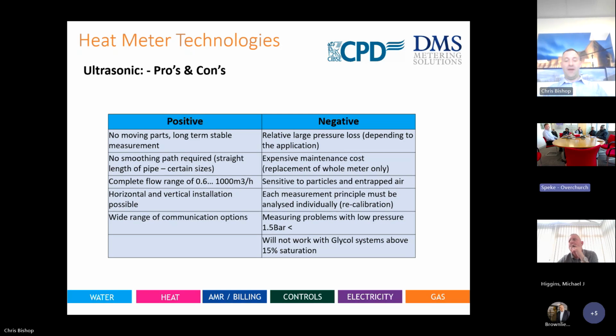Maintenance cost. For example, you have a lot of installers and contractors that shorten cable, they cut cable because the display's up top and the meter's at the bottom, or vice versa, or there's too much cable coiled up and they just want to hide it away. You must never cut any cable on any heat metering device, and really any metering device that's calibrated. All the cables are calibrated for a reason alongside the meter. So the disadvantage to ultrasonics is if you do cut cables, you generally have to replace either the temperature sensors, which is low cost, but if you cut the actual signal cables between the display and the flow parts, you generally have to replace the whole meter.